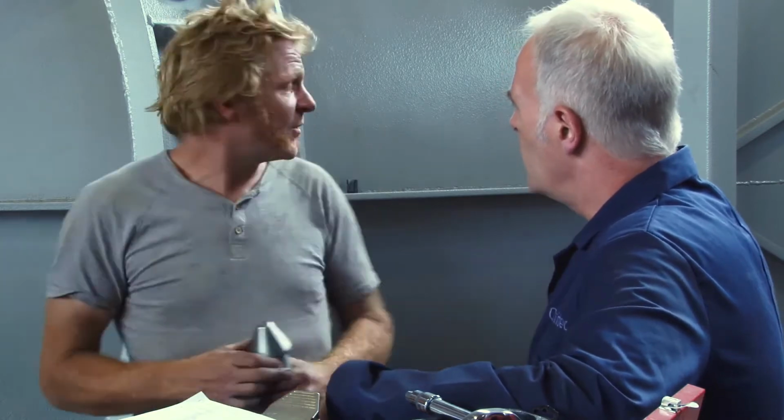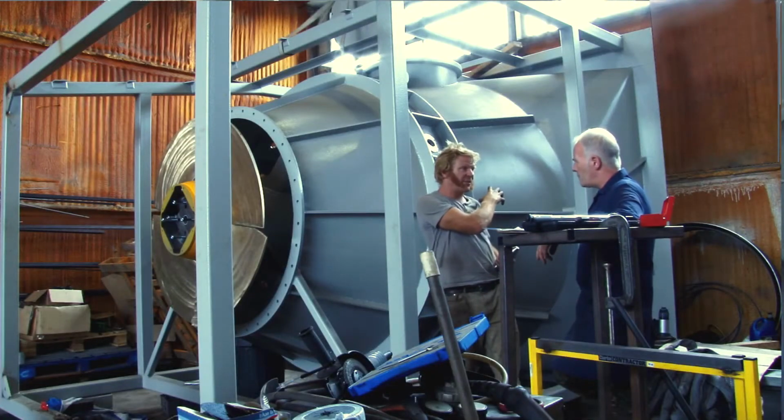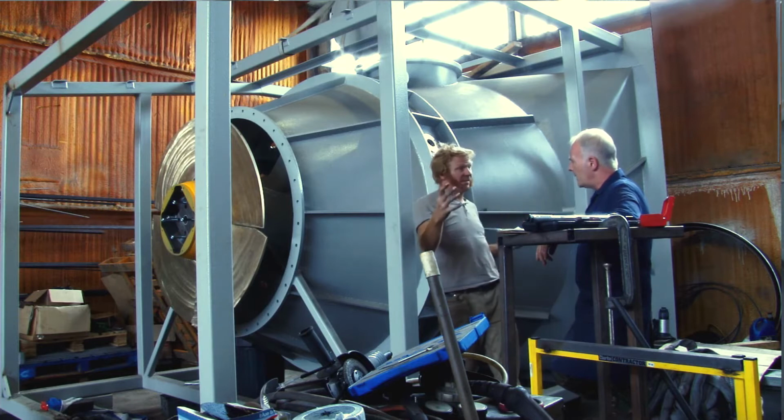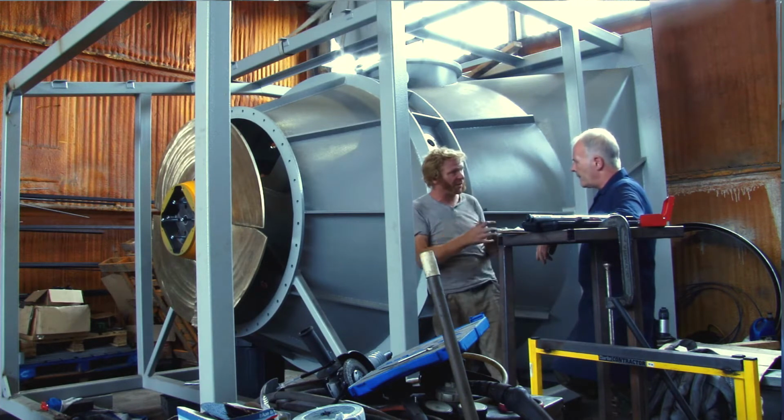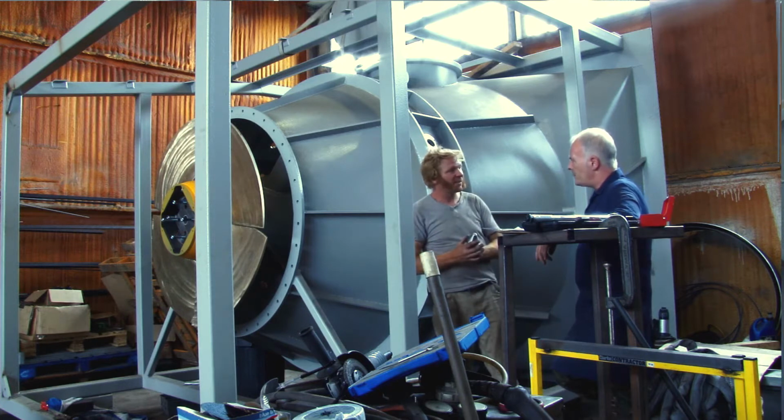The gearbox, we've got no cooling on that, but it's less than 2% loss through the gearbox. So even on 55 kilowatt, we've only got a kilowatt to lose. The casing itself will lose that heat. So you're talking about the internal casing that the generator goes in. That'll sink some of the heat out into the water. And then you've got a water system pumping around the generator to lose heat from that. So it just becomes a lot more efficient, keeps the whole thing cool.